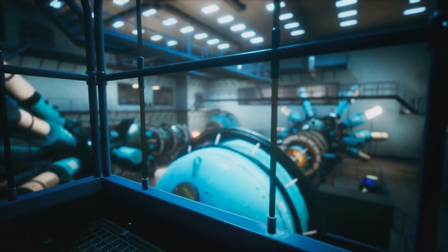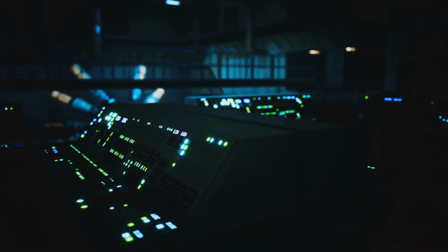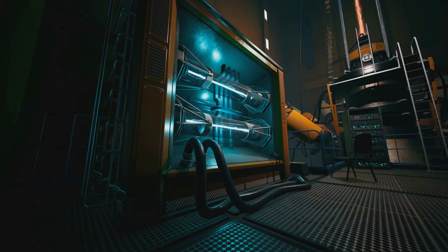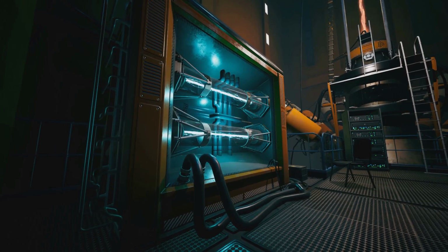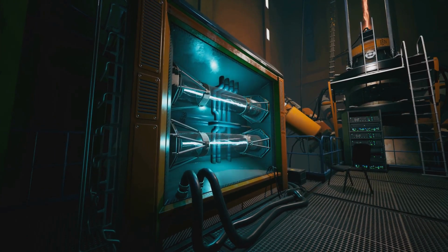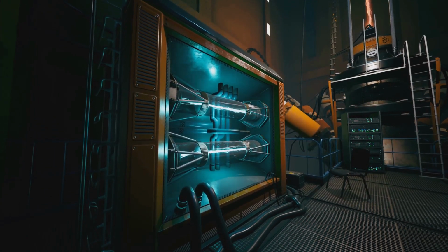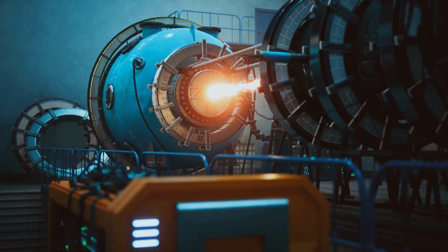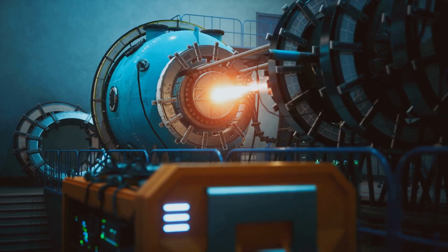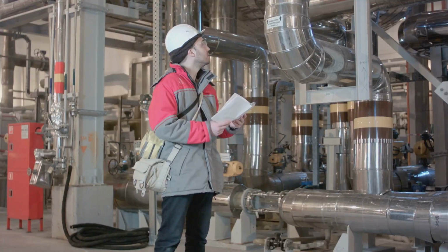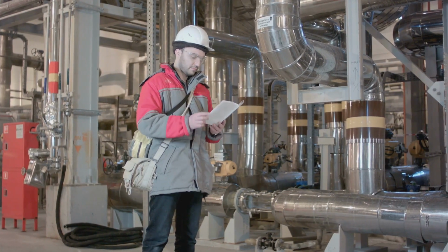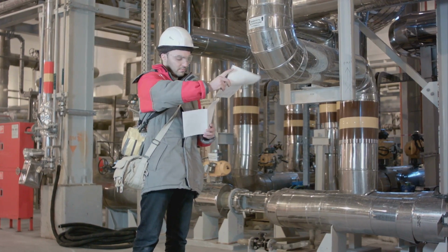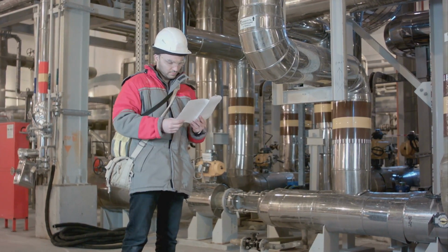Nuclear Instrumentation Testing Program. Nuclear instrumentation (NI) systems in nuclear power plants often suffer from electrical noise issues that can cause plant scrams or threaten on-time startups. To address this, Char Services has developed an NI testing program for source range monitors, intermediate range monitors, and local power range monitors, SRMs, IRMs, LPRMs, in BWRs, and excore nuclear instrumentation in PWRs to help identify NI circuit problems prior to any operability impacts.